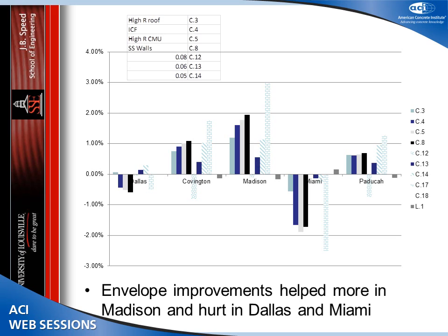increased the energy. In Miami, we got a huge decrease in performance in the building, an increase in energy use, by putting more insulation within the envelope. Kind of counterintuitive, but that has been found by many others and published, and it's actually been confirmed by tests.